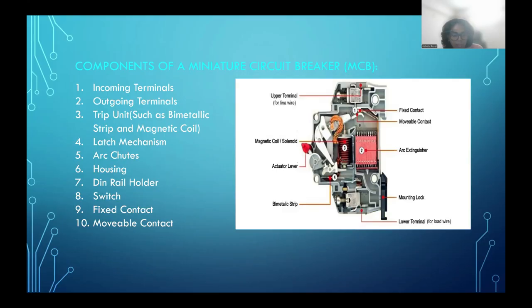Third, trip unit. The bimetallic strip provides thermal protection by bending when overheated due to overload, triggering the trip mechanism. And the solenoid coil provides instantaneous protection during short circuit by generating a magnetic field that activates the trip mechanism. Fourth, latch mechanism. Holds the contacts in position and releases them when tripped.